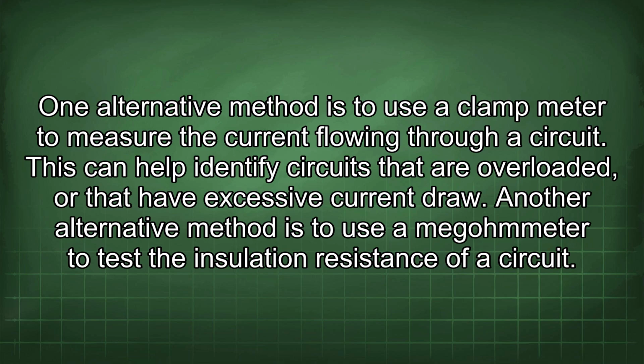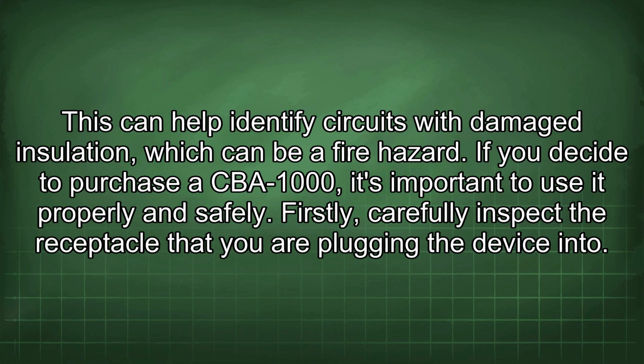One alternative method is to use a clamp meter to measure the current flowing through a circuit. This can help identify circuits that are overloaded or that have excessive current draw. Another alternative method is to use a megohmmeter to test the insulation resistance of a circuit. This can help identify circuits with damaged insulation, which can be a fire hazard.